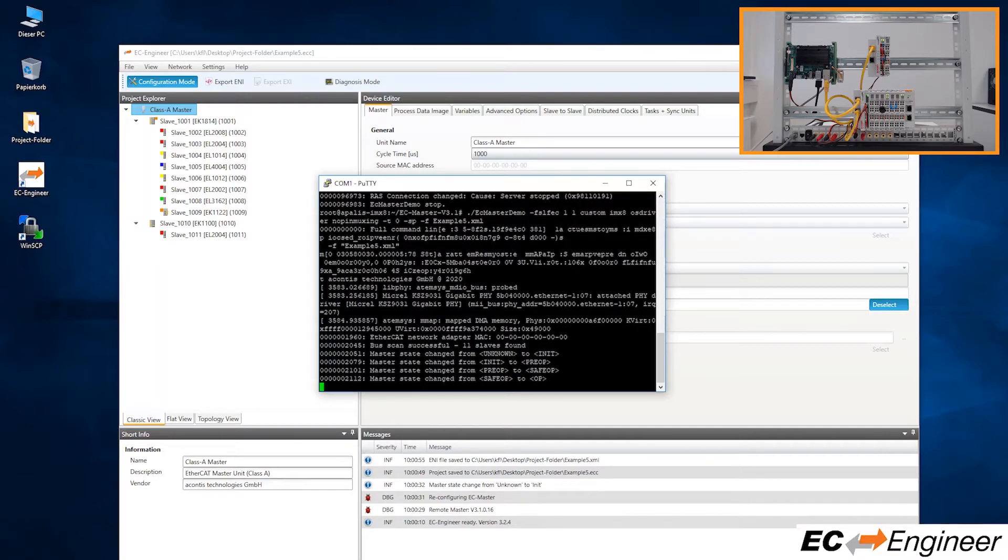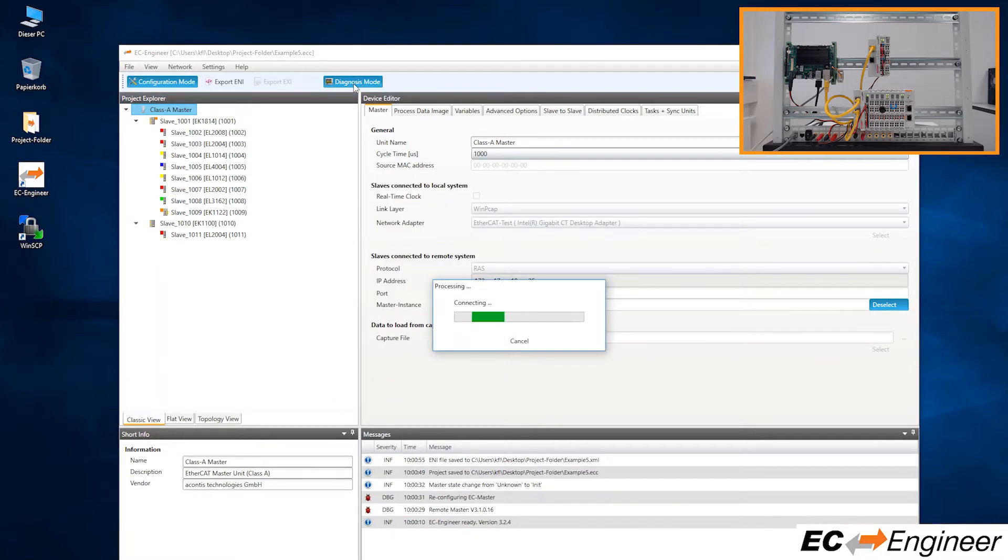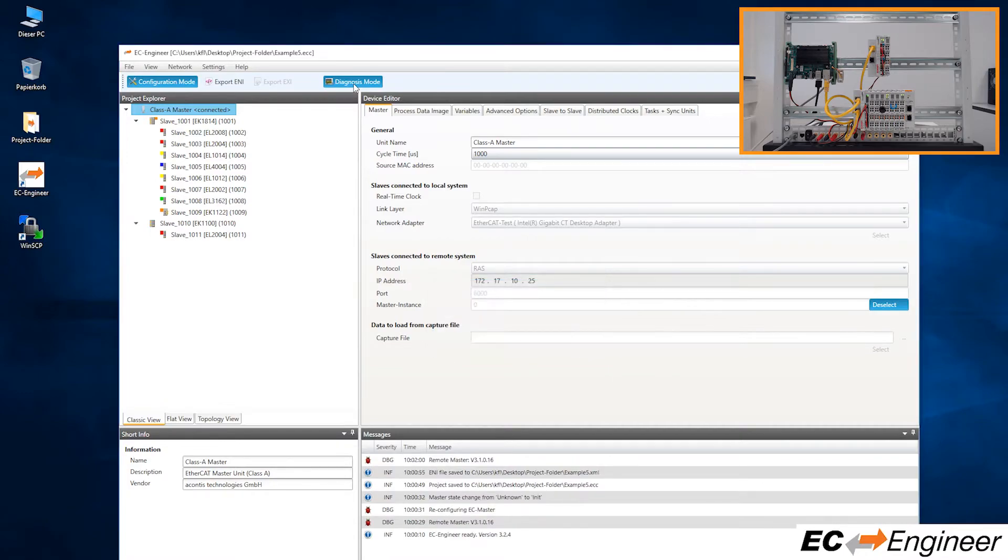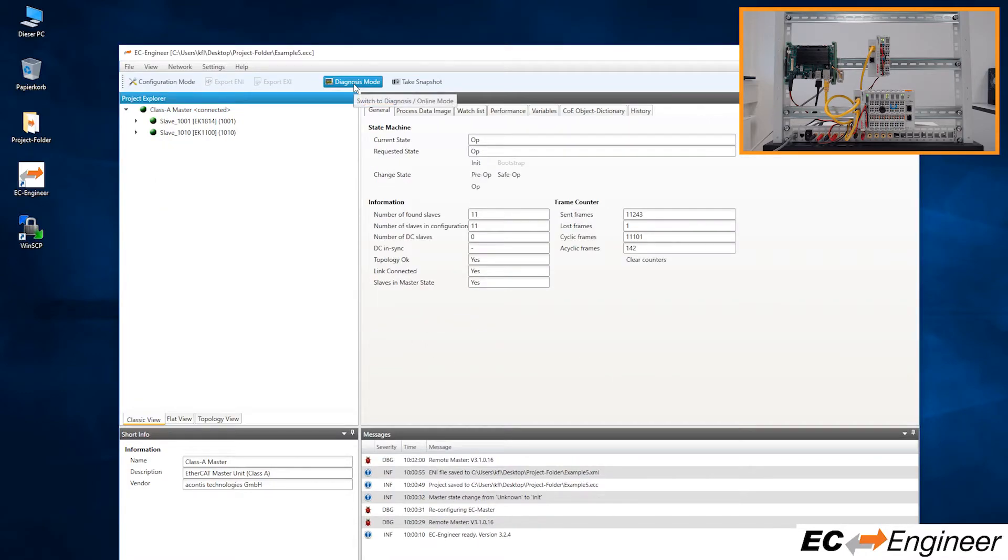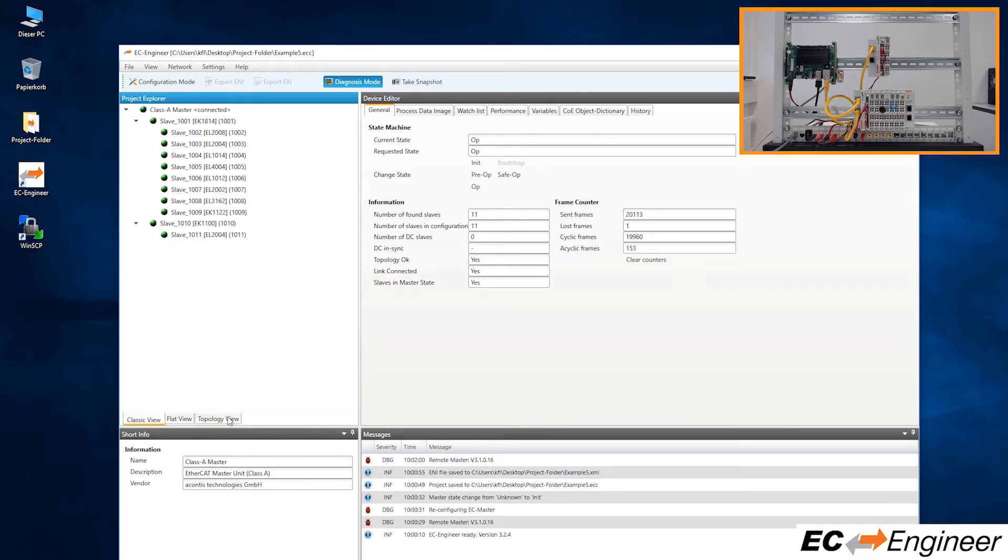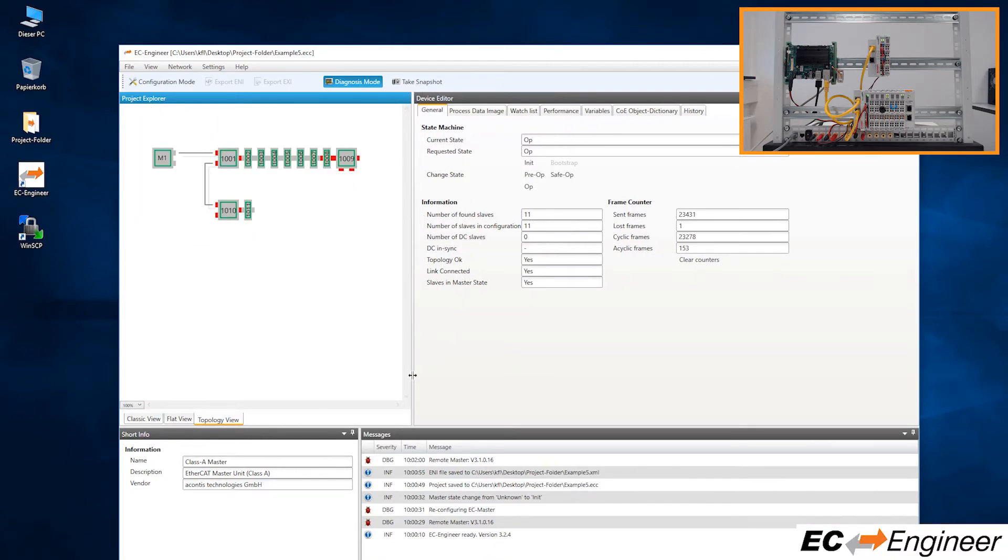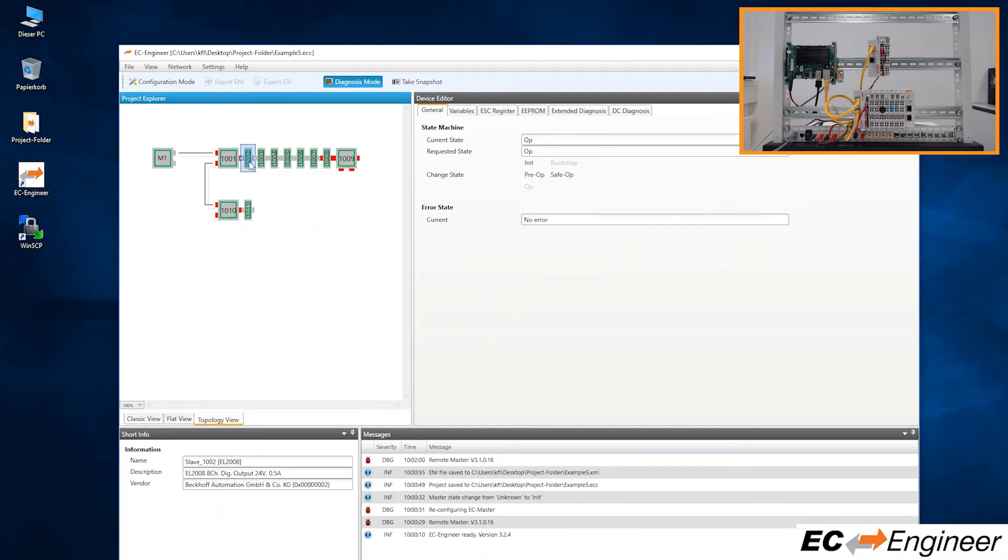Without ever having disconnected EC Engineer, we can switch from the remote configuration mode we were in previously to the remote diagnosis mode by clicking the diagnosis button at the top. We can now see the current state of the network and the slave devices are all green, indicating they are all in operational state. Let's switch to the topology view so that the devices within EC Engineer match the layout of the physical devices as we see them in the lab.